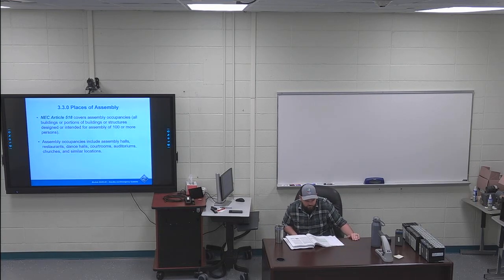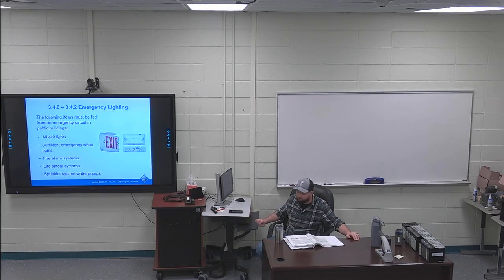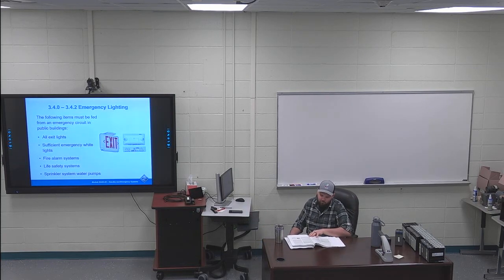Emergency lighting, 340. The sentence before the bullet points is highlighted. In general, the following items must be fed from an emergency circuit in public buildings. I have all the bullet points highlighted. All exit signage, all exit lights, sufficient emergency white lights, fire alarm system, life safety system, sprinkler system, water pumps. Out to the side of that, I wrote no computer equipment. Computer equipment is not part of the emergency circuit in public buildings. You don't have to have computers come back on.